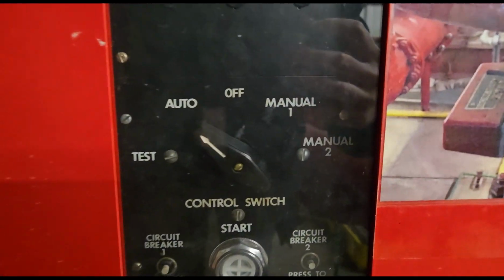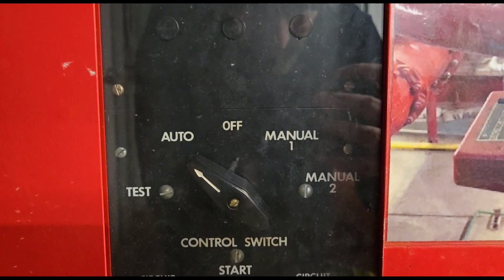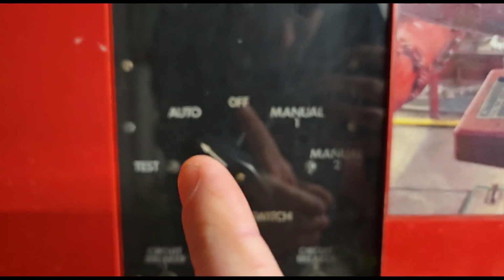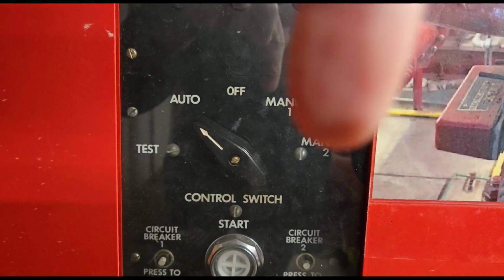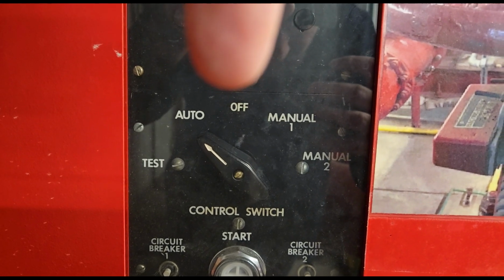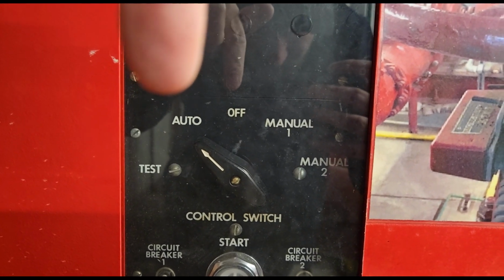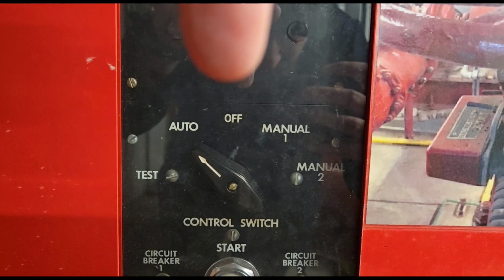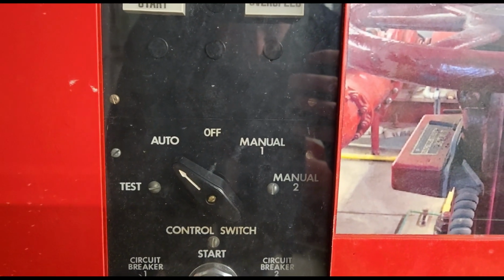We have our dial here. So it's currently set to auto. We're just going to be setting it to off. So there's auto and off. Auto means it's automatically going to turn on when the pressure gets low. And then we're going to switch it to off so it doesn't trigger while we're doing our flow testing.